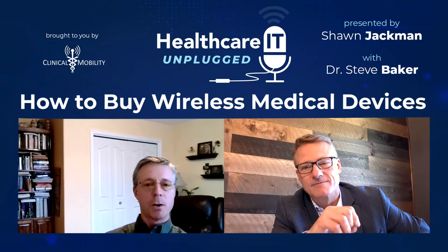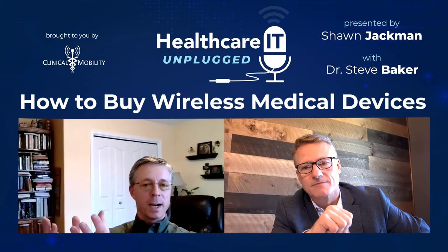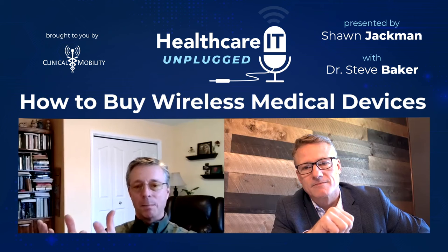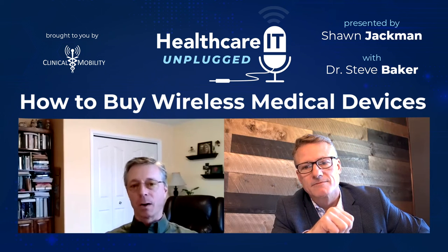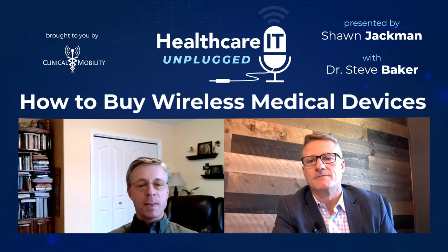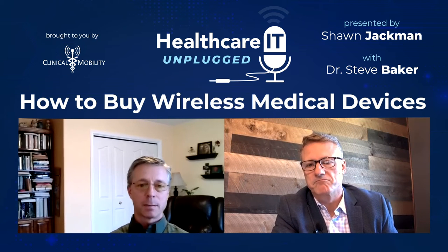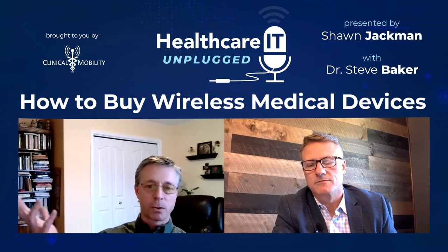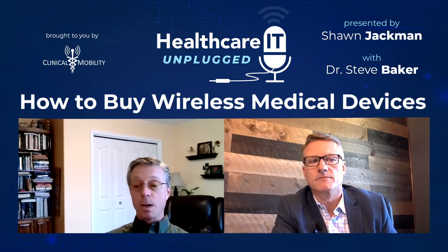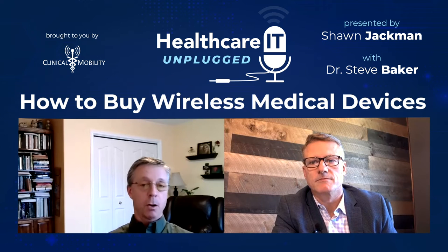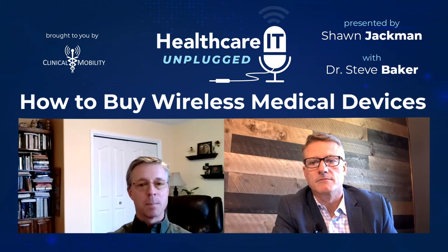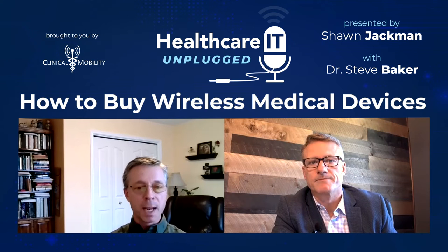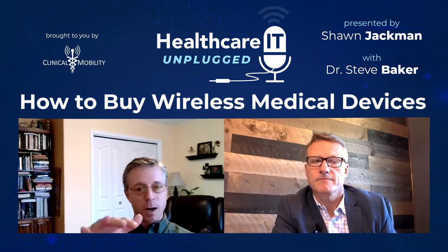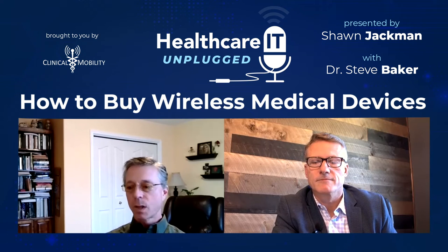But just like, okay, let's say I have this radio and I just get a blob from the radio manufacturer—binary large object—and my Linux kernel just grabs that and puts it into the radio. That's it. So I get the new one that's updated. If it's Bluetooth, it has the SweynTooth vulnerability fixed; if it's Wi-Fi, it has the KRACK vulnerability or whatever the newest vulnerability of the day is fixed. You put it in, turn it on, everything loads and runs. You do some roaming tests. Your risk mitigation shows it doesn't have anything to do with roaming, or this or this. So you test the areas where it may have problems, and after that, you submit your letter to file: here's our justification, here's our risk analysis, here's our testing. That's all it takes.